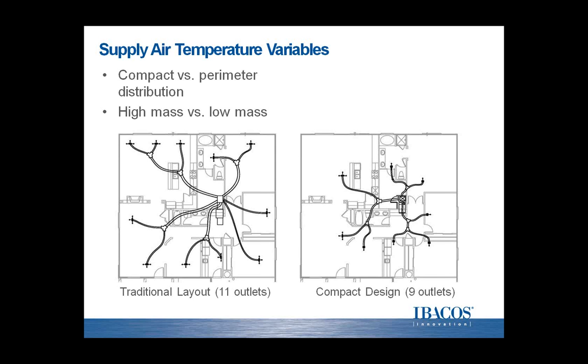And it's kind of hard to tell your occupant, well, you just furnished the room wrong, right? By putting a high sidewall in, there's not much of an option for them to cover or block that device. But I agree, perimeter systems do work well, and they do maintain comfort. There are some challenges with them. The other downside is you've got more material associated with it and longer duct runs. So in trying to increase the velocity of the ducts, you're paying a penalty for the velocity by increasing the static pressure in those ducts, and having shorter duct runs helps to neutralize that increased static pressure associated with higher velocities.